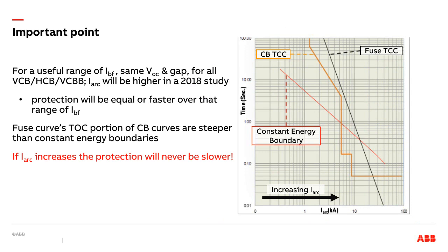When you look at protective devices, whether they're circuit breakers, which are shown by that orange curve, or a fuse, which I sort of simplified and grouped together with this black line here, typically an I to the fourth characteristic, and you compare with that red line, which is called a constant energy boundary. Notice that this is arcing current. You'll see that the circuit breaker overcurrent element, the fuse overcurrent element, are both steeper than this red line.